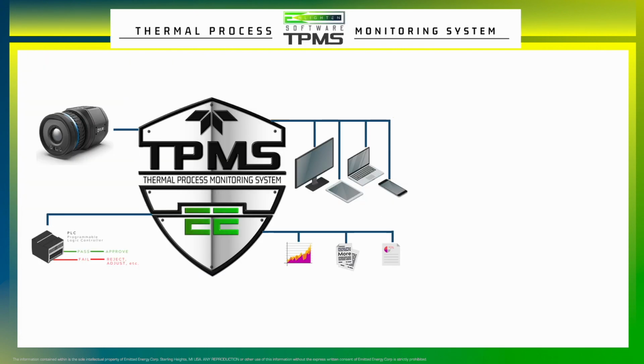The thermal process monitoring system is a process monitoring system designed specifically to automate the food manufacturing safety and packaging validation. It is a system that employs only the best Teledyne FLIR infrared automation cameras to provide a non-contact temperature measurement, collecting literally millions of temperature readings per second. Each individual frame of picture that the camera takes is between 76,000 and over 300,000 temperature measurements in a single image. Now, those images can then be saved to be recalled later for additional advanced post-processing and analysis.